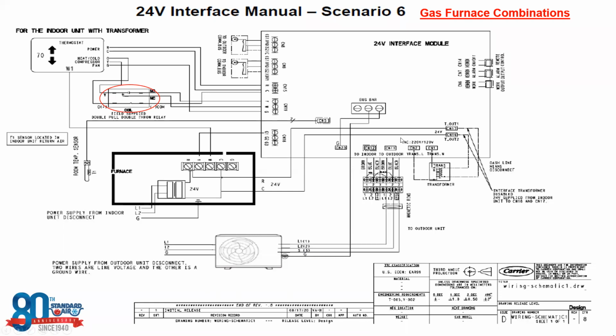Okay. Now you'll see on here, just like we had with the FB models, the supplied transformer that steps down this line voltage to 24 volts AC is going to get removed, just like we did before. And we're going to supply that 24 volts from our gas furnace because we have a transformer that's already stepping down incoming voltage to control voltage, in this case 24 volts AC. So at the terminal connections for your thermostat at the indoor unit for your gas furnace, you're going to take your R and C, and you're going to feed that directly into these two terminals, just like we did with the FB4 model. So nothing's changed in that regard.